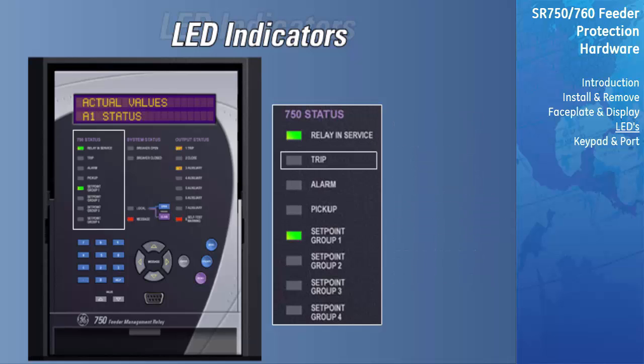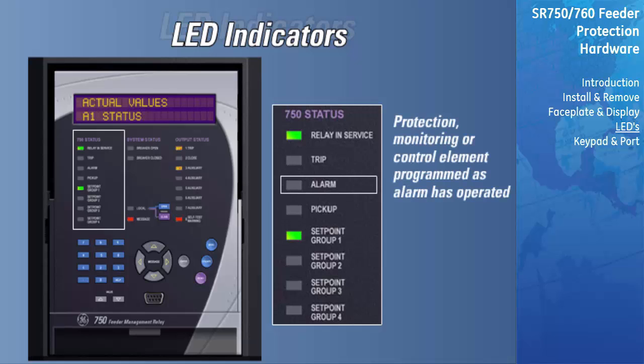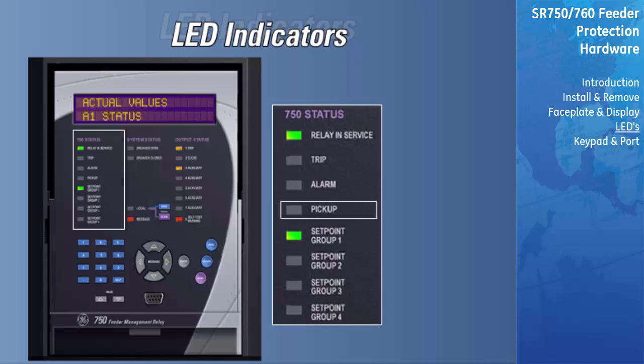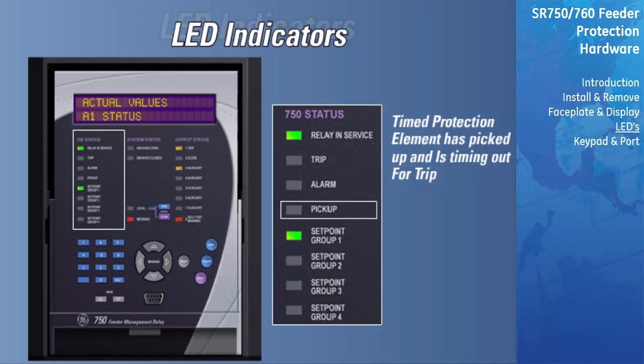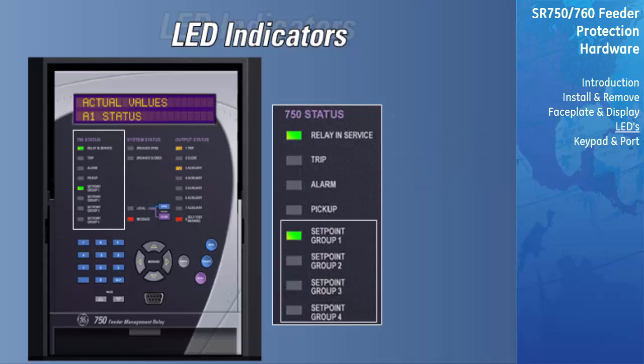The Trip LED indicates that a protection element that is programmed as a trip function has operated. The Alarm LED indicates that a protection element that is programmed as an alarm function has operated. The Pickup LED indicates that a timed element, such as the timed overcurrent, has picked up and is timing out towards a trip. The Setpoint Group 1 through Setpoint Group 4 LEDs will indicate which of the 4 sets of protection elements is being used to protect the system.